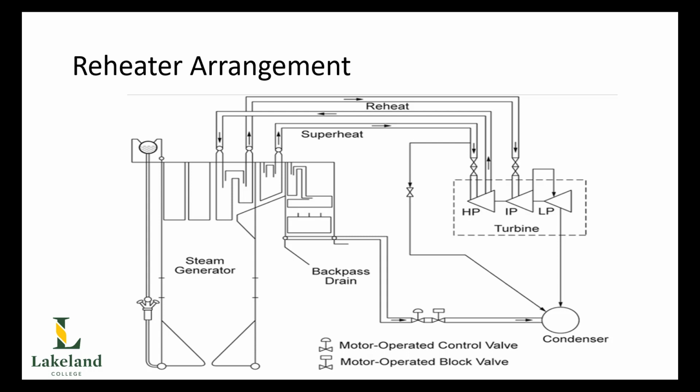And you can see in this particular diagram that we have here a two-stage reheater that's both in the convective and the radiant section. The right-hand side being protected there by the nose wall. The boiler will now reheat the steam temperature back up to 538 degrees C, and it now goes back into the beginning of the intermediate pressure stage of our turbine. From here, it will expand through the intermediate pressure and the low pressure stages, where once again, the pressure and the temperature will reduce and the volume will increase. We're now going to extract as much useful work energy out of our enthalpy as possible in our turbine to achieve the highest efficiency that we can.